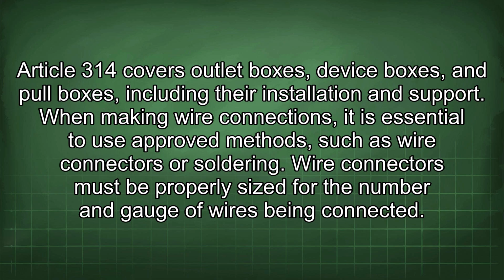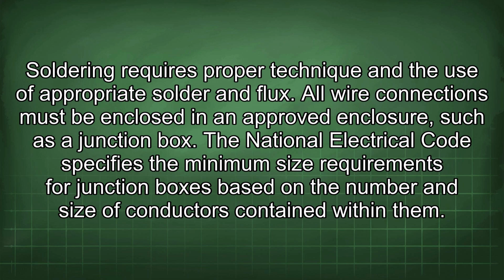Article 314 covers outlet boxes, device boxes, and pull boxes, including their installation and support. When making wire connections, it is essential to use approved methods such as wire connectors or soldering. Wire connectors must be properly sized for the number and gauge of wires being connected. Soldering requires proper technique and the use of appropriate solder and flux. All wire connections must be enclosed in an approved enclosure, such as a junction box.